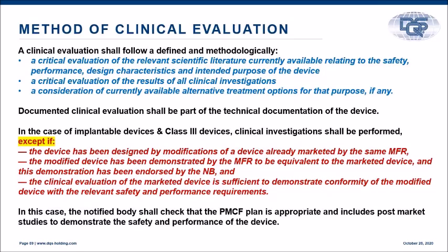So the guidance, MEDDEV 2.7.1 revision 4 for clinical evaluation, has been published considering the requirements of MDR as well. So it covers many aspects of the requirements from MDR in terms of the expectations on clinical evaluation and post-market clinical monitoring.